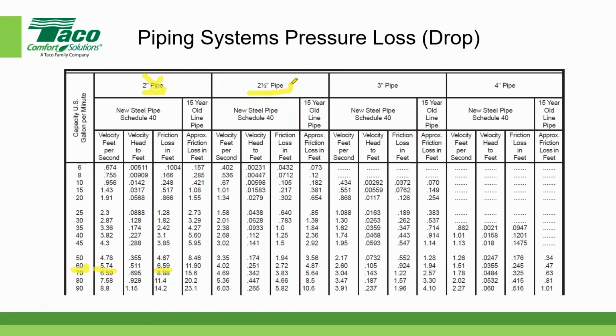So I go over here to the 2.5-inch pipe. Again, I go to roughly 60 gallons per minute. Obviously I'm going to meet the criteria of less than 8 feet per second, which in this case is 4.02. And my pressure loss is 2.72 feet per 100 feet. So that's why I decided to use 2.5-inch pipe, and there's my 2.5-inch pipe value up there. Now that I know what the pipe size is, I'm going to erase all this stuff.